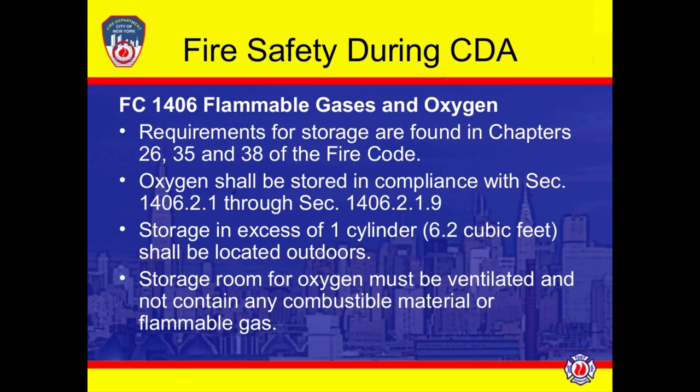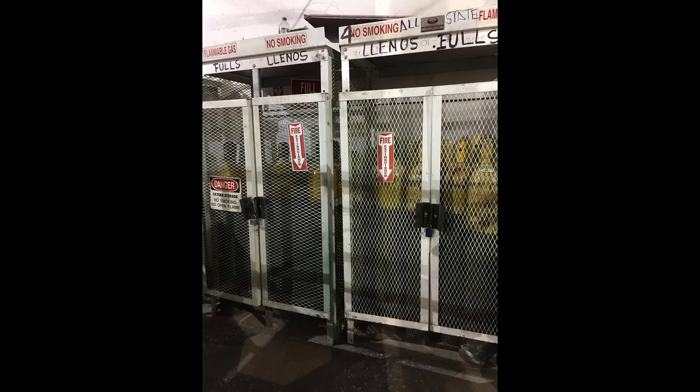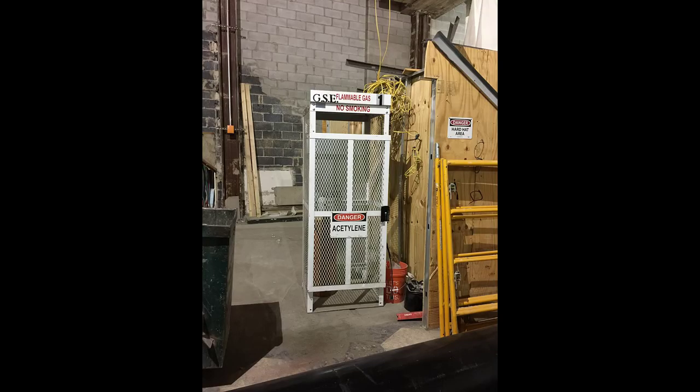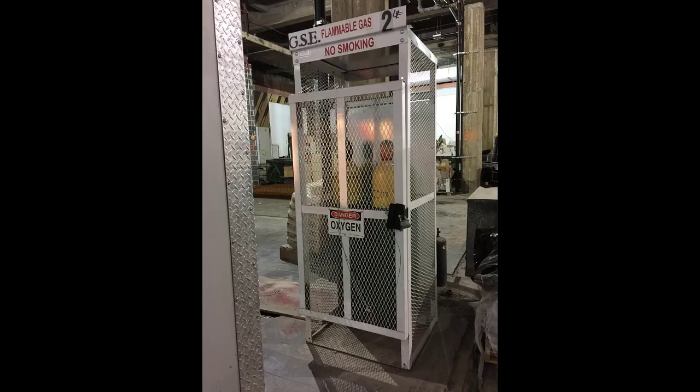Flammable and combustible compressed gases and liquids require an FDNY storage permit. You can contact the district office to obtain one. All flammable and combustible gases and liquids must be clearly identified on the container. MSDS, or Material Safety Data Sheets, are required for all chemicals and gases brought onto the site.